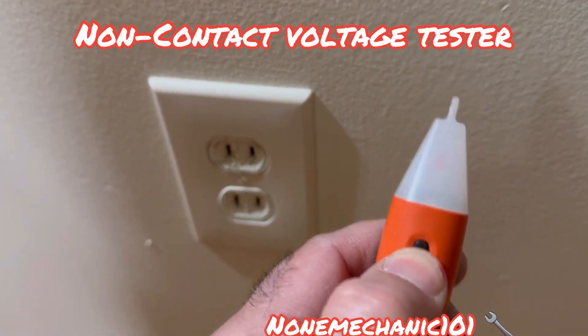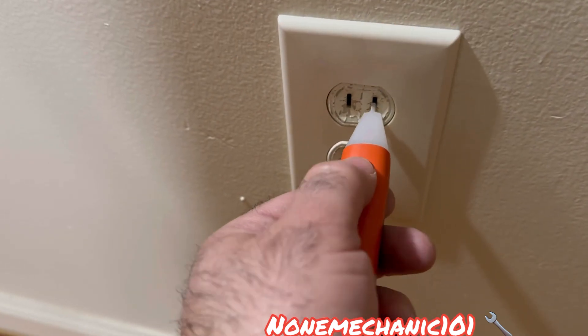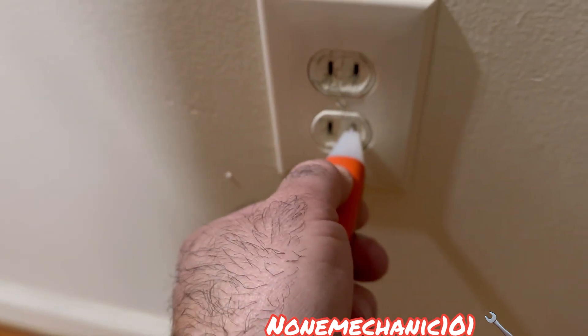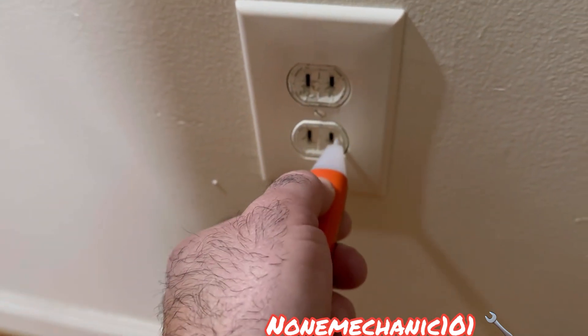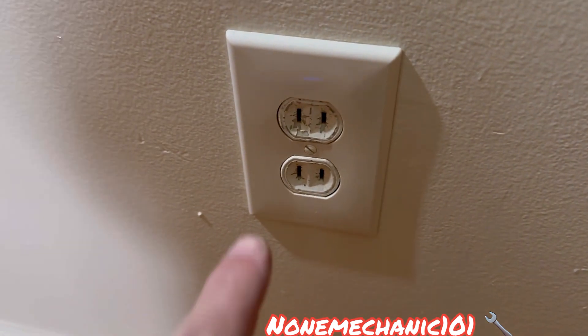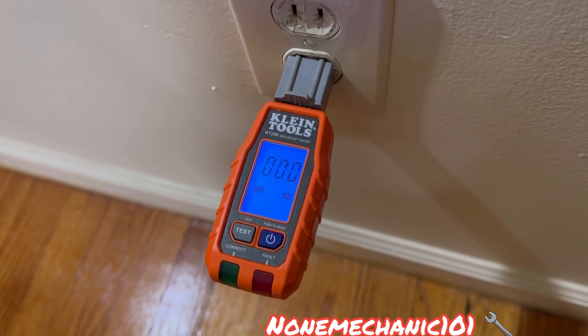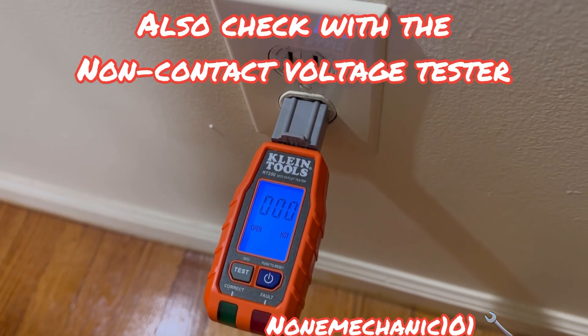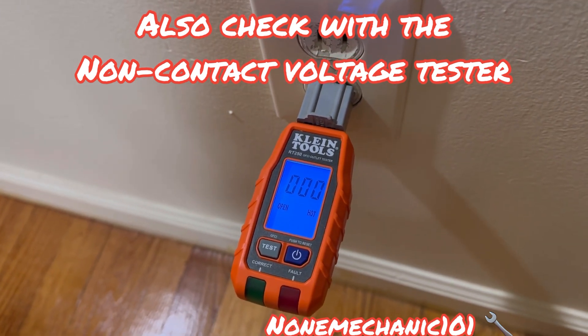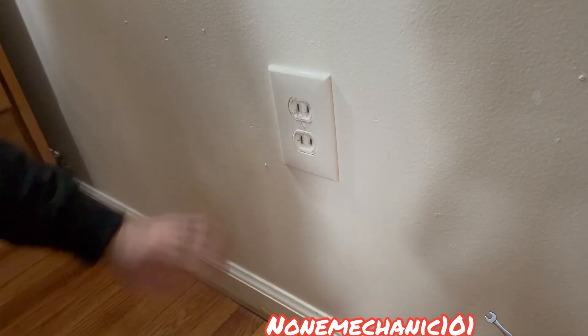I already know this power tester works because I checked it on the other ones. We press in here and it's showing no volts at all. I'm still going to find the circuit breaker that belongs to this — I have them all marked — turn it off and be right back. I turned off the circuit breaker and put the Klein tool again to make sure there's no power, and it's right at zero now.